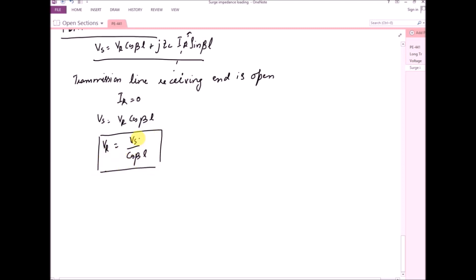So the receiving end voltage is the ratio of the sending end voltage and the cosine of βL. The maximum value of cos(βL) is equal to one, so if it is any value other than one, the receiving end voltage will be greater than the sending end voltage — this is known as the Ferranti effect. This normally occurs when there is a lightly loaded transmission line or the receiving end is open.